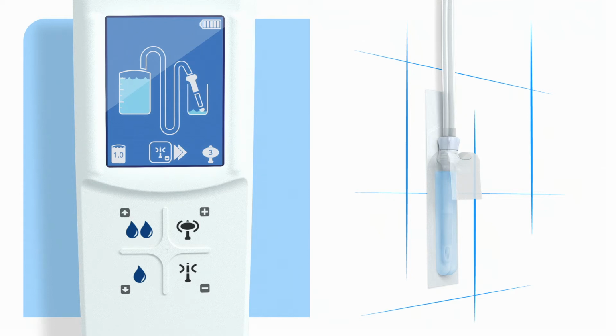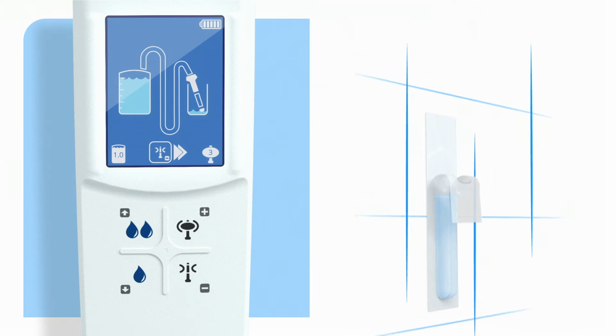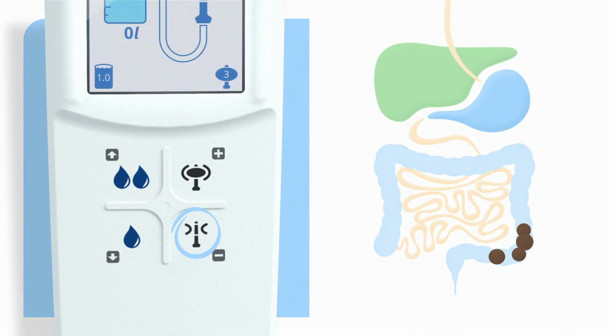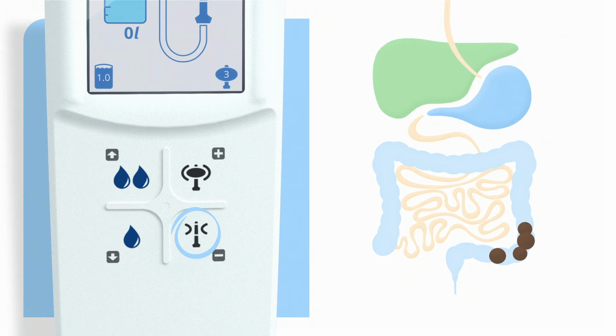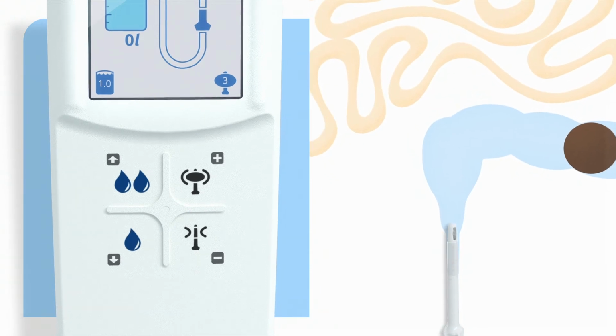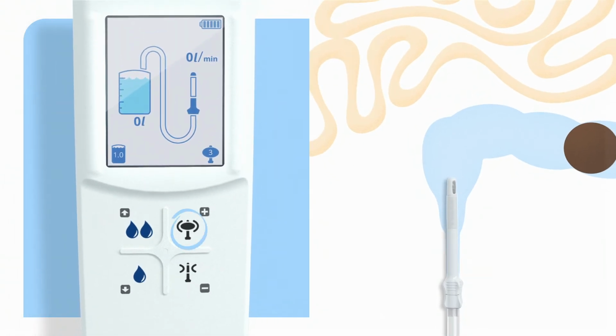Remove the rectal catheter from its packaging. Remember to keep the package, you'll need it for the disposal of the rectal catheter. Press the Deflate button to proceed to the installation mode. Now, insert the rectal catheter carefully. Press the Inflate Balloon button. You should inflate the balloon only as much as you need to prevent leakage during irrigation. You can stop the inflation at any time by releasing the button. Gently pull the catheter slightly down to seal the rectum.